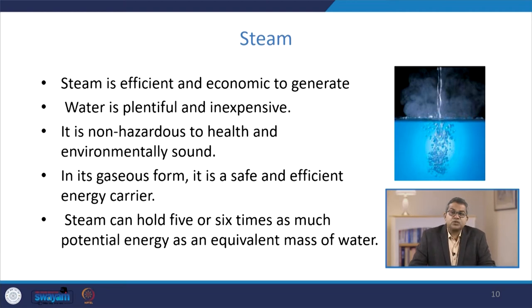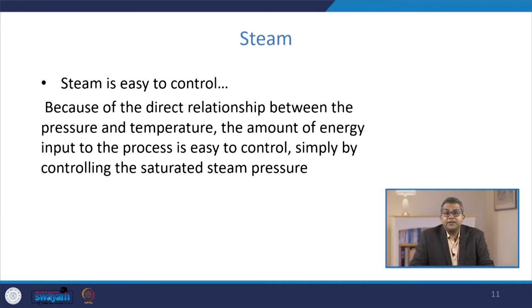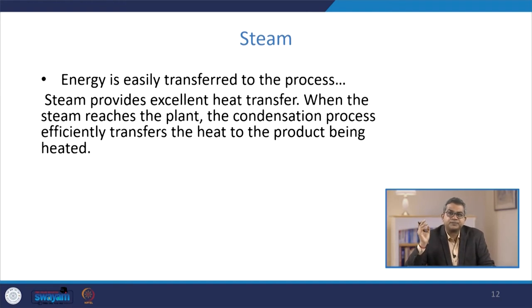It is non-hazardous to health and environmentally sound. In its gaseous form, it is a safe and efficient energy carrier, and trust me, it is very economical in this aspect. Above all, steam can hold 5 or 6 times as much potential energy as an equivalent mass of water, just courtesy of latent heat. Steam is also easy to control because we have a direct relationship between pressure and temperature. The amount of energy input to the process you can easily control simply by controlling the saturated steam pressure.